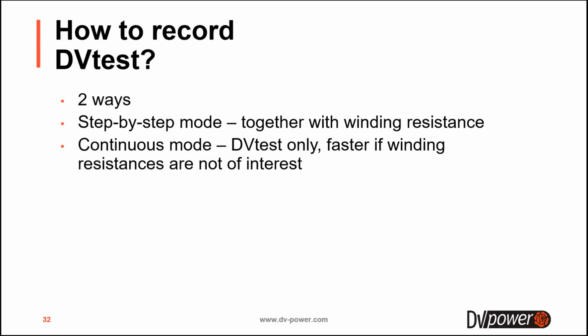So you can do it in these two ways. You can do it together with the winding resistance. It will take the same time as it would take if you just measure the winding resistance. So without any additional time, besides the winding resistance test, you can get information about the on-load tap changer. Or if you want to do it quickly, you can do continuous mode, and very, very fast, in a few minutes, you can record all the transitions of the OLTC.